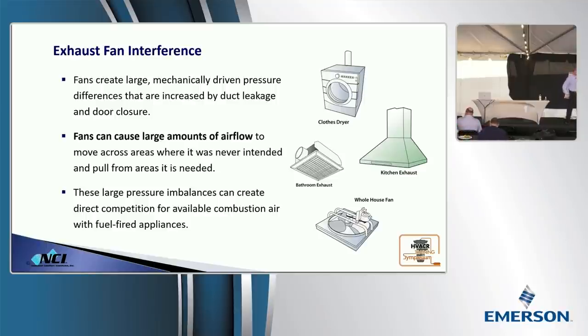What about a whole house fan? Do you guys live in areas where a whole house fan will fail combustion air every single time? So be aware that if you have a whole house fan and you're not opening every single window up, you're in trouble. Now, let me go back to what we talked about on stack effect, exfiltration and infiltration. With whole house fans, they tell you to raise all the windows.